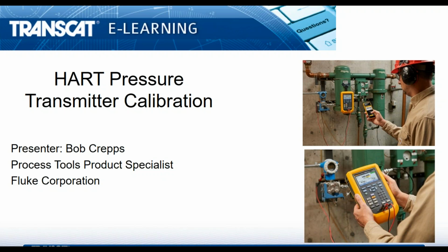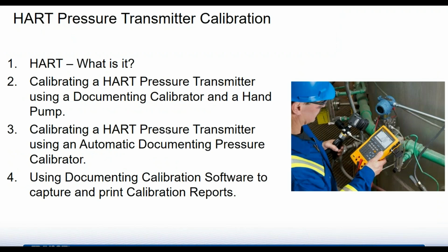As the Process Tools Product Specialist, I get a lot of calls about pressure calibration, and I thought today I'd share with you some of my experiences and talk about different types of pressure calibration. So, 4 main topics I'd like to talk about today. First, just a quick discussion of HART. What is it? Second, go through calibrating a HART pressure transmitter using a documenting calibrator and a handheld pump. Third, we'll go through calibrating the HART pressure transmitter using an automatic documenting pressure calibrator. And finally, I'll go over documenting calibration software and how it works with the pressure calibrations.